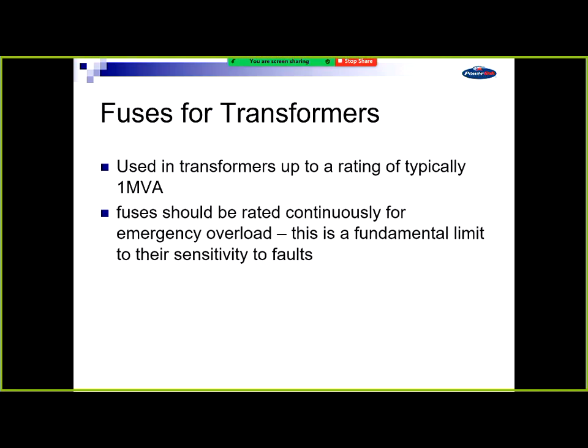Fuses are typically used in small transformers. We use them in our local supply transformers. A typical substation for PowerLink has our transformers, a delta tertiary with a low rating, and we take off the local supply for the AC for the substation off those delta tertiaries. That's 70 or 80% of our substations.